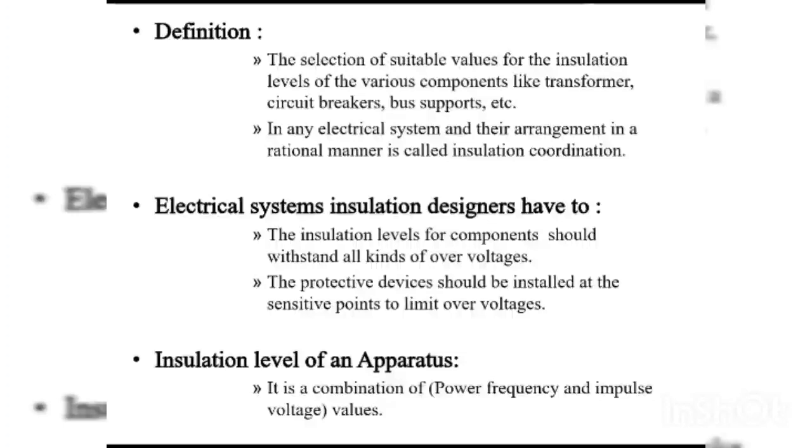In electrical system insulation design, the insulation levels of components should withstand all kinds of over voltages. The protective devices should be installed at sensitive points to limit over voltages for safety purposes. The insulation level of an apparatus is a combination of power frequency and impulse voltage values.